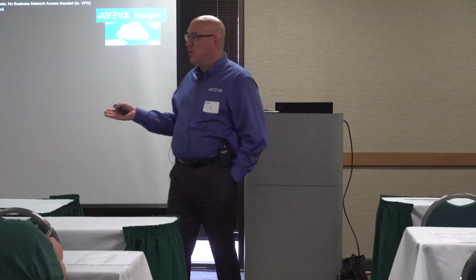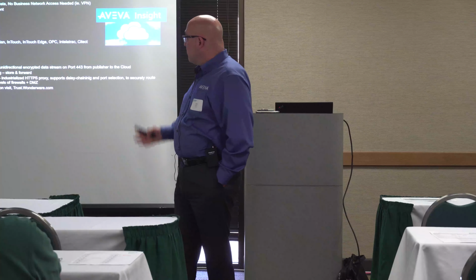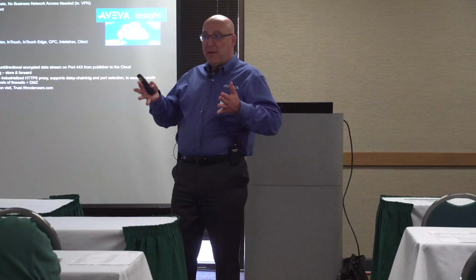For cloud-based applications, SQL is not a cloud protocol. It's just not allowed up in the cloud. So we use a newer retrieval protocol called OData. It's a RESTful API that allows you to get data out of the historian and put data into the historian, so it's fully programmable. You can create tags, delete tags, and send data into them via all kinds of mechanisms. You can just use a little HTTP GET and put data into the cloud historian. Get data from everything, little JSON pairs.